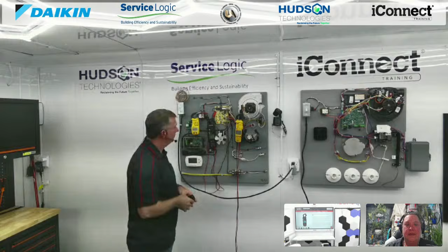As we start increasing our motor efficiency, we'll see drastic differences, getting up into the 70s and 80s. That's the reason those shaded pole stacks actually get warm. This motor right now has warmed up significantly because of the inefficiency of a shaded pole, and it doesn't even have ball bearings. It's got sleeve bearings, so they could even be dry from hanging - the oil could have run out, and that motor may be performing extra inefficiently.